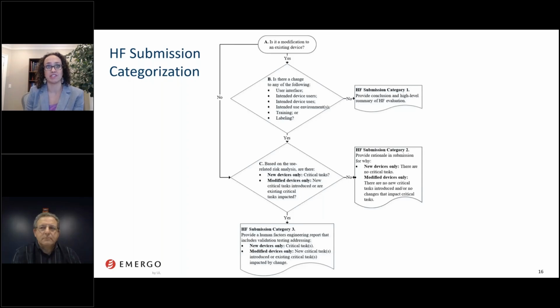If there are differences in the user interface, the users, the uses, etc., that'll take you down to decision point C, which is where you do your risk analysis and consider critical tasks. Then depending on the outcome of that item, you either go into category 2, if there's not an impact or no additional critical tasks, or if there are new or impacted critical tasks, you find your way to HF submission category 3. So despite the simple structure of this flow chart, manufacturers will need to do some legitimate human factors engineering work, and in some cases, some fairly heavy lifting, to be able to accurately react in particular to decision points B and C.